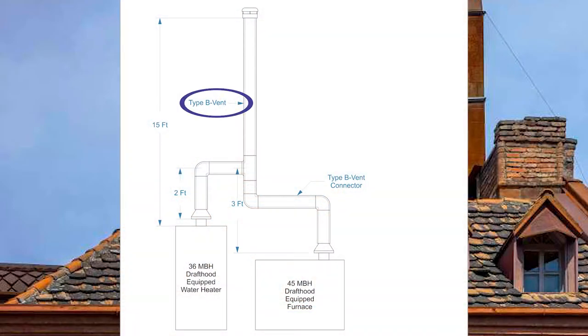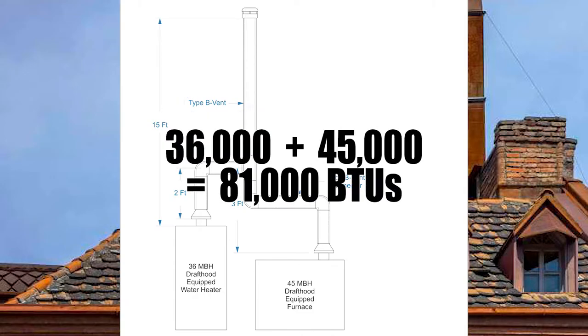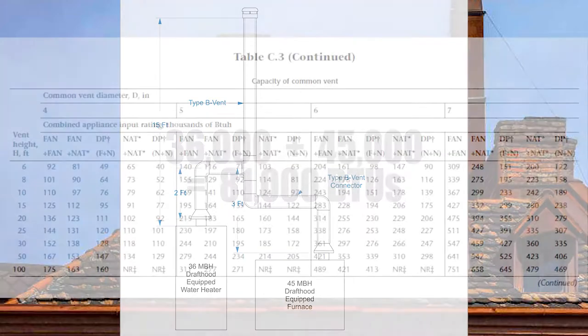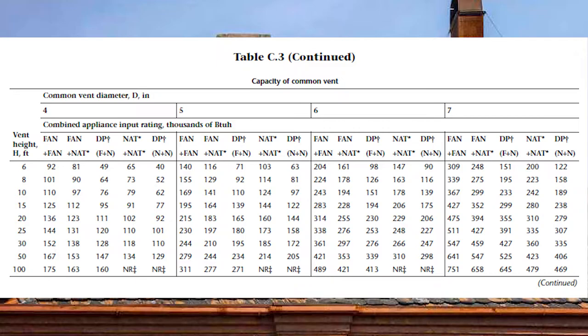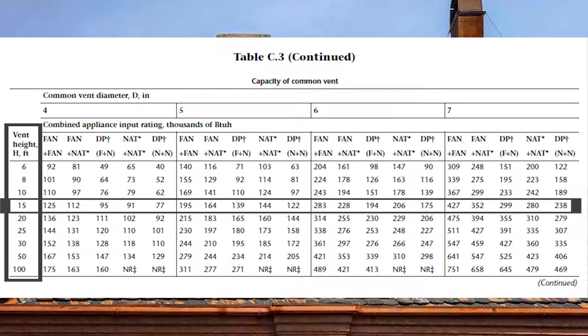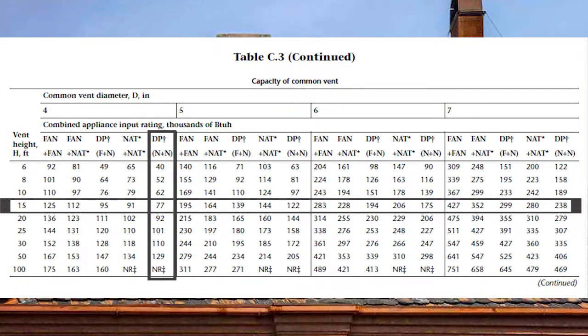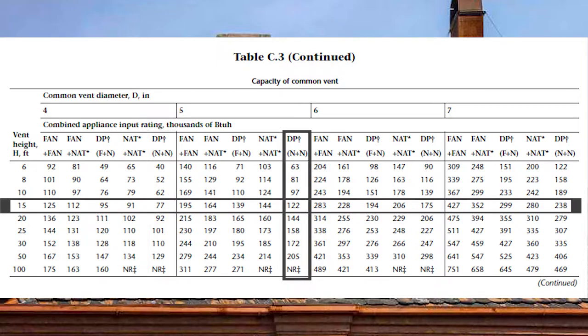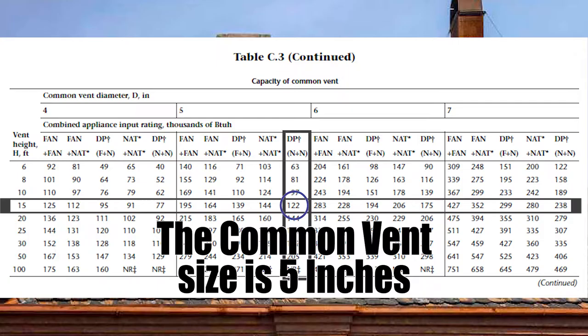Now for the second part we need to size up the common vent, but first we need to add up the total BTU load: 36,000 plus 45,000 equals 81,000 BTUs. Turning to page 200 in the codebook to size up the common vent using table C3, I come down to the 15-foot vent height and across to DP N plus N in the four-inch column — only good to 77,000 BTUs. Moving to the five-inch column at DP N plus N, that's good to 122,000 BTUs. The size of our common vent will be five inches.